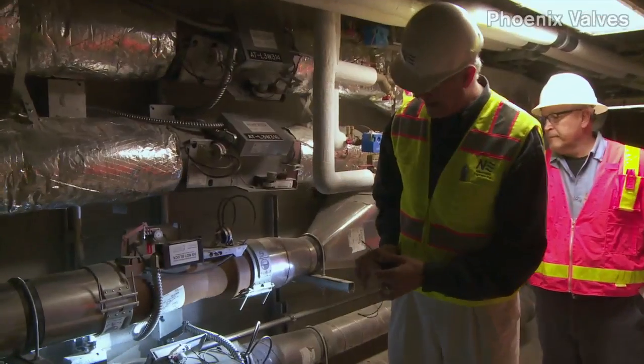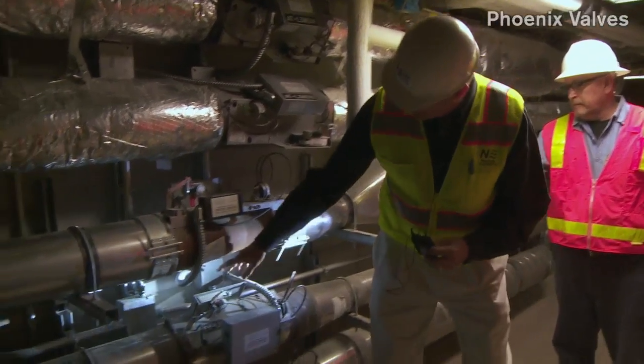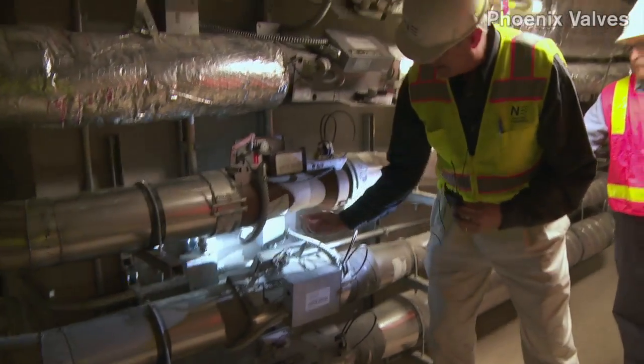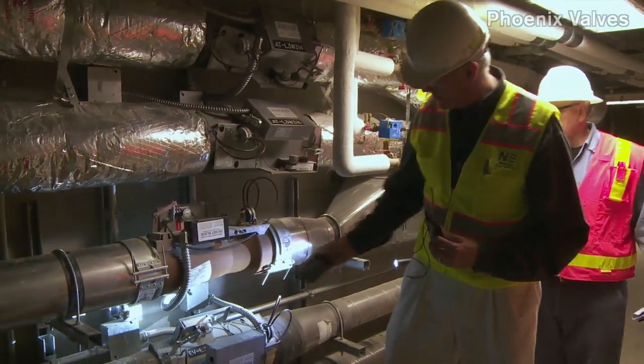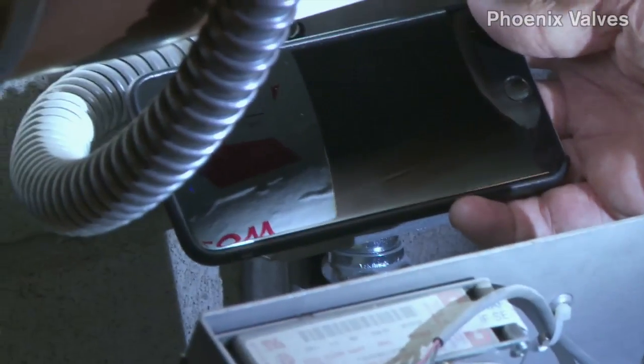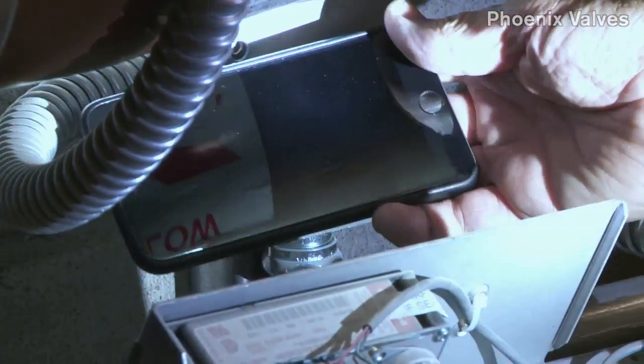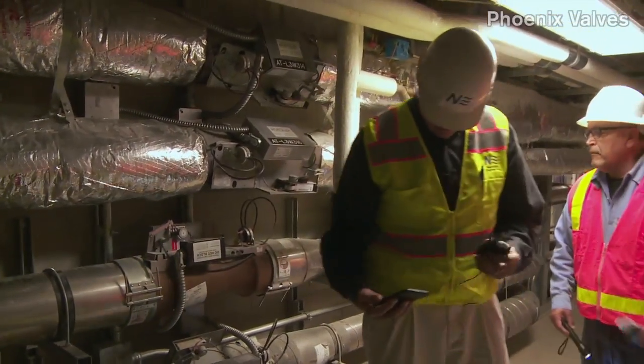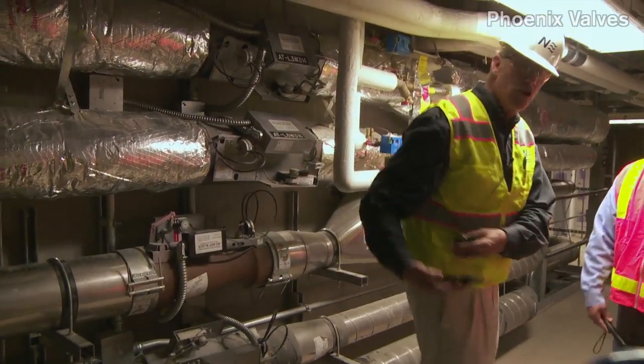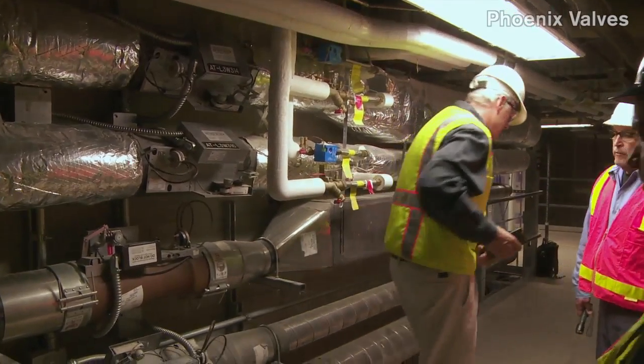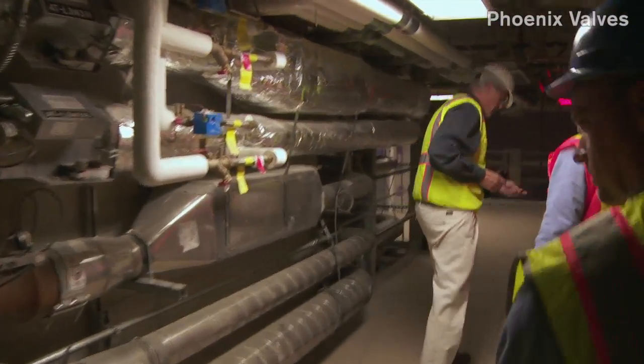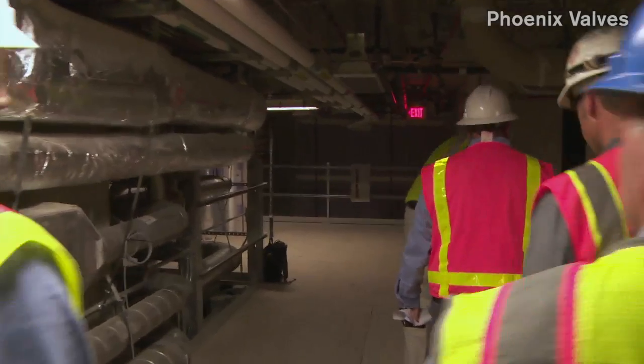So this won't be an issue, but every valve has a directional airflow arrow on it. Maybe the reflection off my, yeah, you see, can you see that white label with the red arrow? Yep. So you get a white label on a horizontal valve. Of course, the air has to be flowing the right direction. That's important. We check that all out during startup. But when the valves are vertical, the label is a different color. So if we go over to the vertical valves over here, sorry, Mike, man.